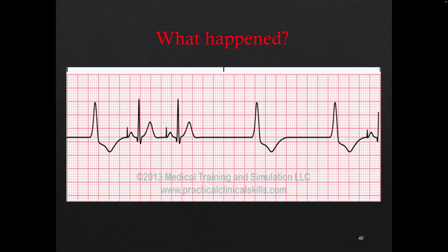So let's just say I'm going to use number 1. Say your sensitivity was at 1, go up to whatever the next is. I think these go like 1.2 and then 1.4 and then 1.5 then 2. Just go up to the next sensitivity and see if it goes away, if it starts sensing properly. So remember, the higher the sensitivity number, the less sensitive, to make it not oversense. If it's undersensing, you want to bring the number down and make it more sensitive so it sees it, right?